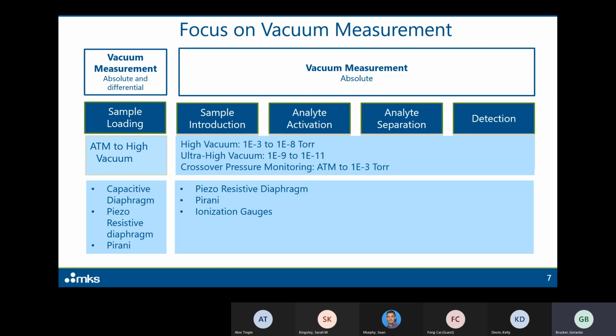Both absolute and differential pressure measurement are required here for the reasons I told you before, right? Before I open up a load lock port to the atmosphere, I have to make sure that the pressure inside the load lock is not much lower than atmospheric, or I'm going to get an inrush of gas, in which case the differential pressure measurement is required. On the rest of the building blocks, typically the measurement is an absolute measurement. Very often these measurements are happening at high vacuum, anywhere from 10 to the minus 3 to 10 to the minus 8 torr. If you are dealing with surface analysis instrumentation, sometimes you even have to go into the ultra high vacuum level, 10 to the minus 9, 10 to the minus 11.